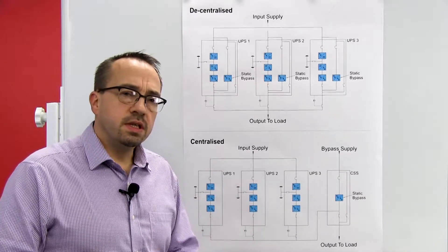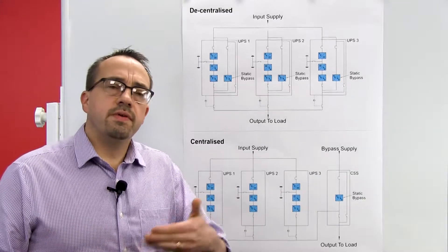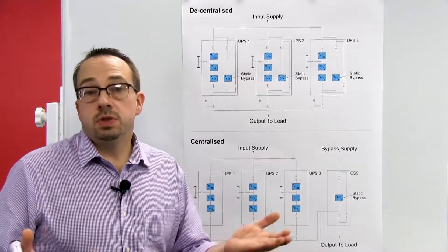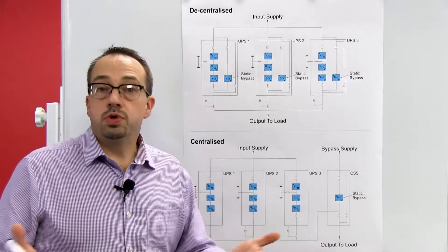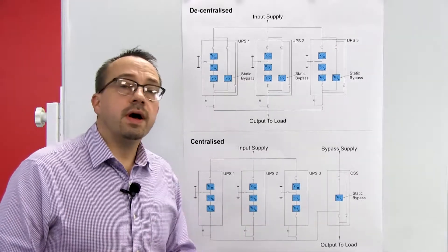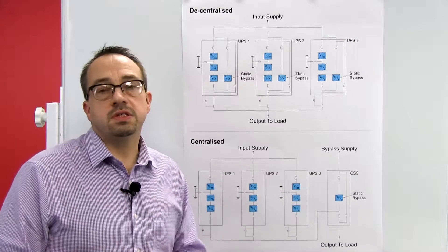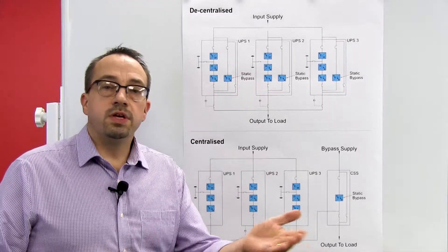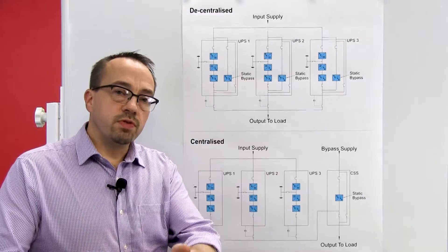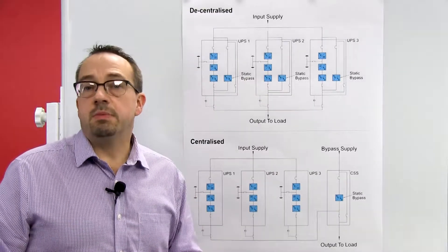In addition to this, the static bypass can also be utilized to clear issues on the outgoing side of the UPS, such as overloads or short circuits. Should an issue arise, the UPS system will simply transfer the load onto the static bypass, allow the issue to be resolved, and then transfer the load back onto the inverter completely seamlessly.